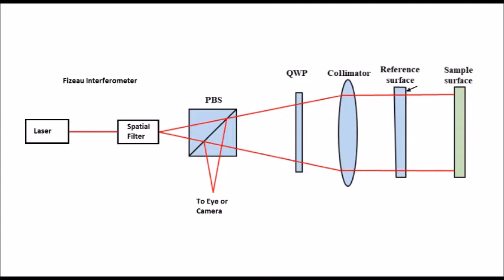The polarization is rotated 90 degrees and then reflected 90 degrees into your IR camera. A normal beam splitter will lose about 50 percent of the light on each pass and you would end up with only 25 percent of the light, whereas a PBS and quarter wave plate would lose very little. For alignment, a small corner cube is swung into the collimator's beam and it produces another dot on the screen, and dots from the reference and part are aligned to it.